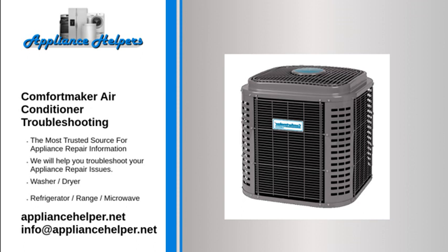Comfortmaker condenser fan motor does not run. If the capacitor is defective, the fan motor might be noisy, overheat, or not run at all. To determine if the capacitor has failed, inspect the capacitor. If the capacitor is bulging or leaking, replace it.